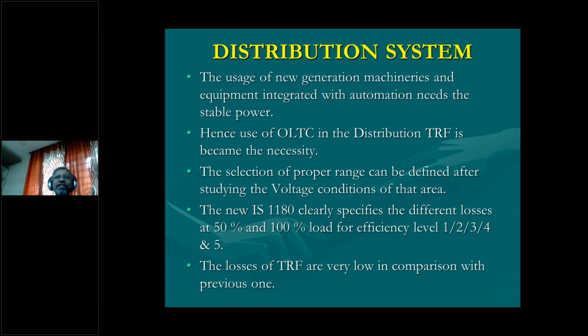Change the tap, then start the transformer again. In that case, there is always a shutdown to change the tap, which is practically not possible. Hence, OLTC is on load. OLTC is controlled by the AVR, automatic voltage regulator. So you can control the voltage accordingly.